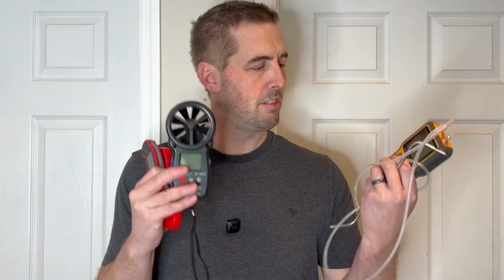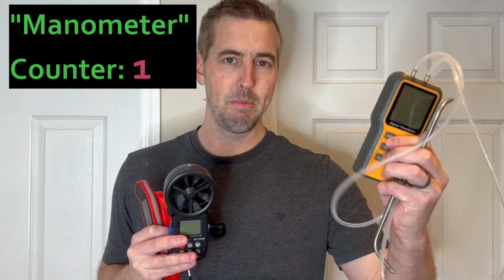So you might be wondering, okay, how are we going to test these filters? Well, with some instrumentation, of course. We've got our digital manometer here to allow us to measure static pressure. We've got our anemometer allowing us to measure airflow. And then we've got some really fancy meat thermometers to allow us to measure temperature. So the combination of these are going to allow us to gauge the impact of the filter on our furnace performance.